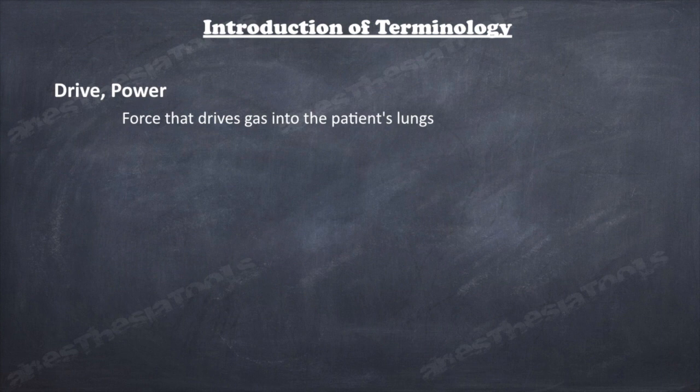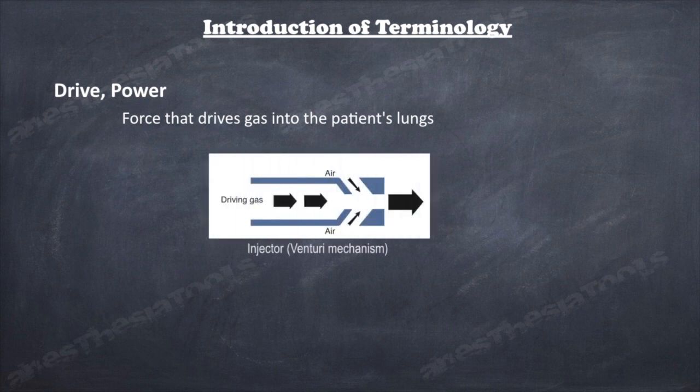First, power source—the force that drives gas into the patient's lungs. It can be either compressed gas or electricity. Many currently available anesthesia ventilators are pneumatically powered but electronically controlled. The driving gas is oxygen, air, or a mixture. A clinical point to remember: using a gas cylinder to power a pneumatic ventilator will quickly deplete the gas supply.